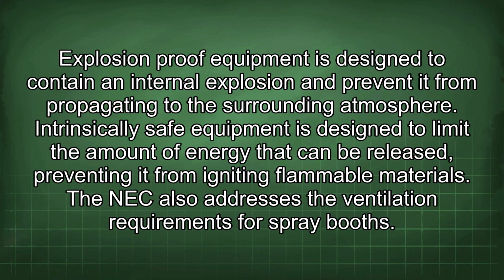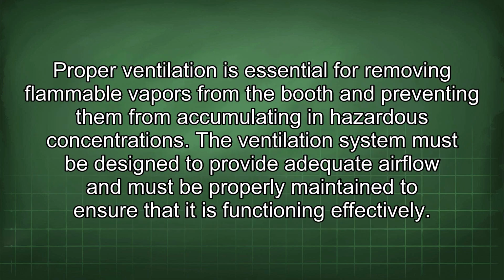Explosion-proof equipment is designed to contain an internal explosion and prevent it from propagating to the surrounding atmosphere. Intrinsically safe equipment is designed to limit the amount of energy that can be released, preventing it from igniting flammable materials. The NEC also addresses the ventilation requirements for spray booths. Proper ventilation is essential for removing flammable vapors from the booth and preventing them from accumulating in hazardous concentrations. The ventilation system must be designed to provide adequate airflow and must be properly maintained to ensure that it is functioning effectively.